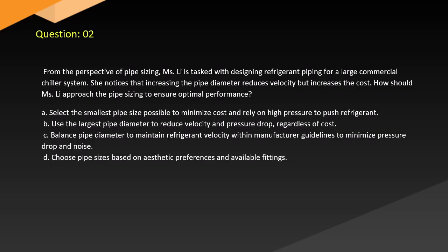Question 2. From the perspective of pipe sizing, Ms. Li is tasked with designing refrigerant piping for a large commercial chiller system. She notices that increasing the pipe diameter reduces velocity but increases the cost. How should Ms. Li approach the pipe sizing to ensure optimal performance?